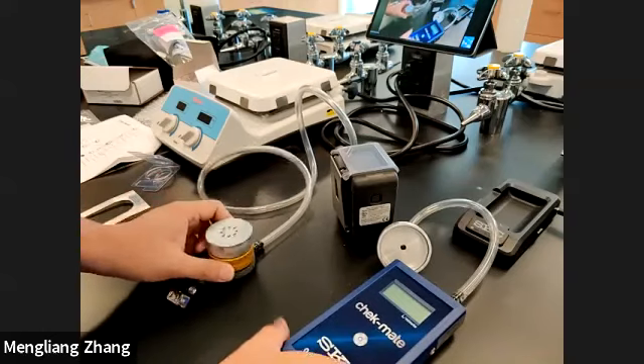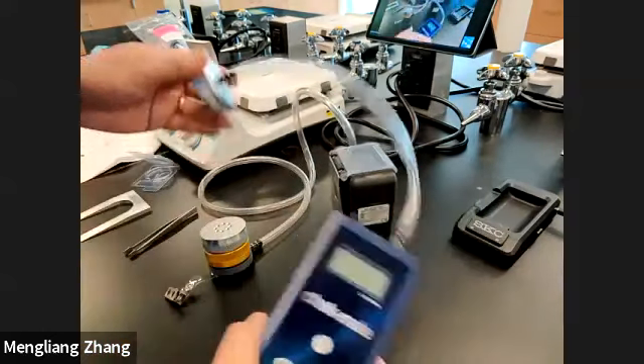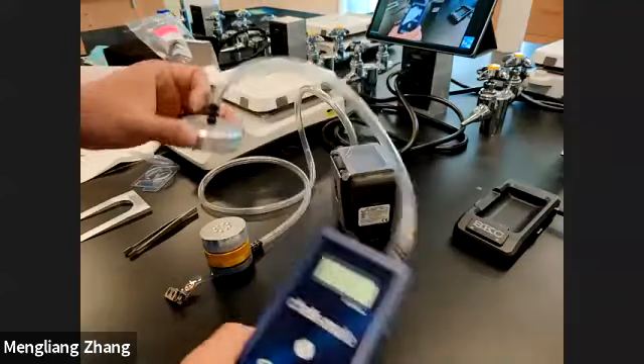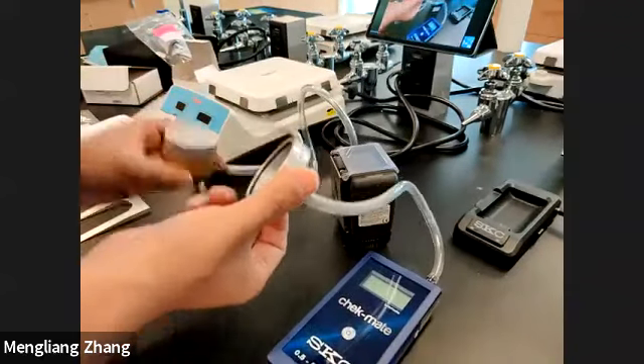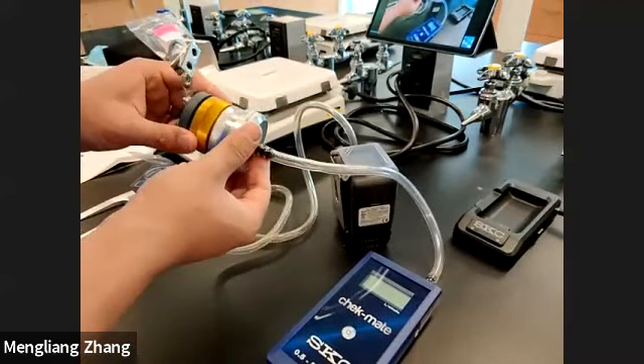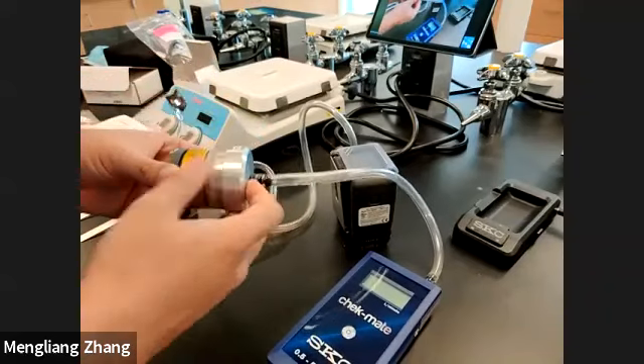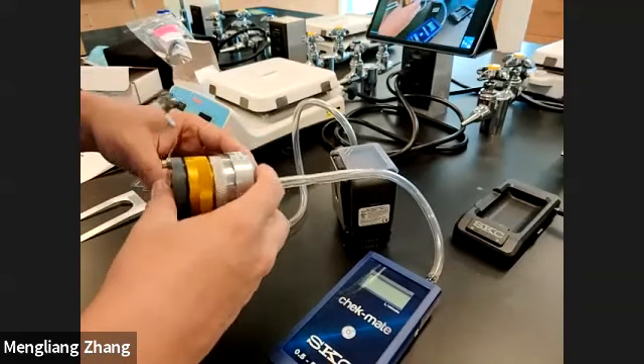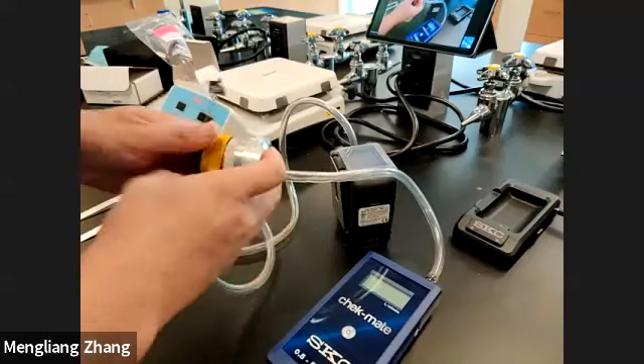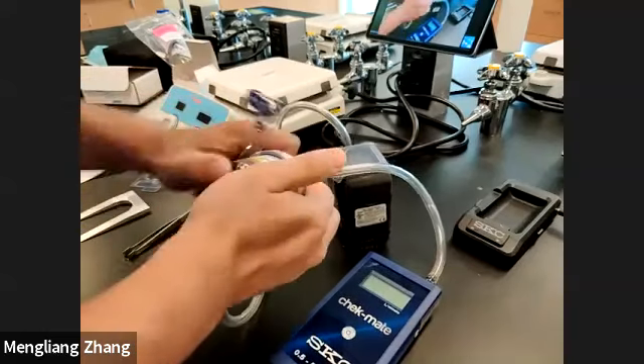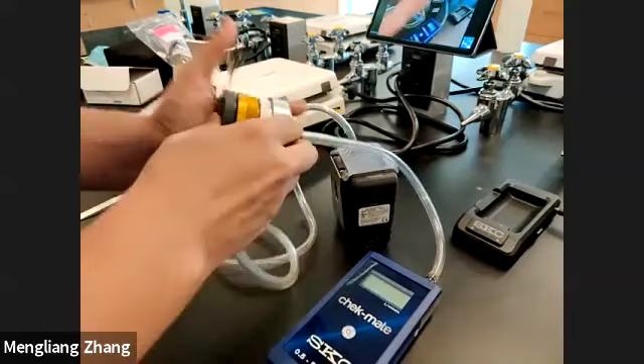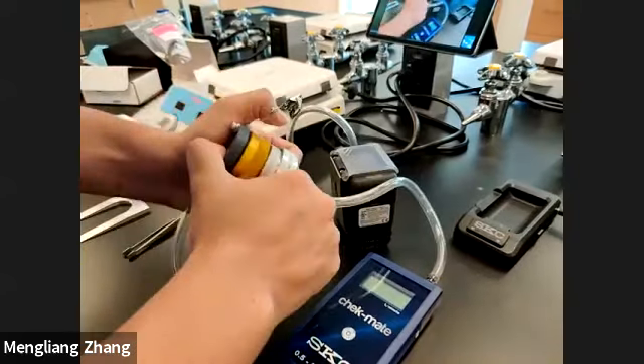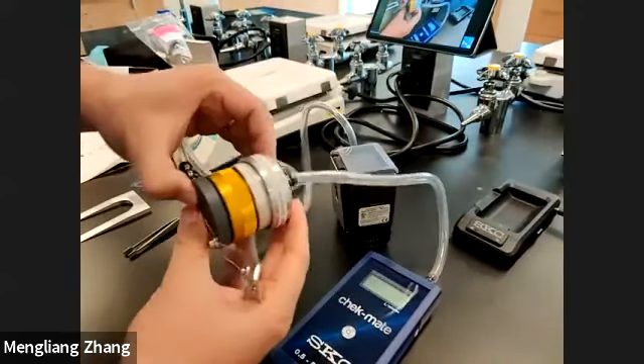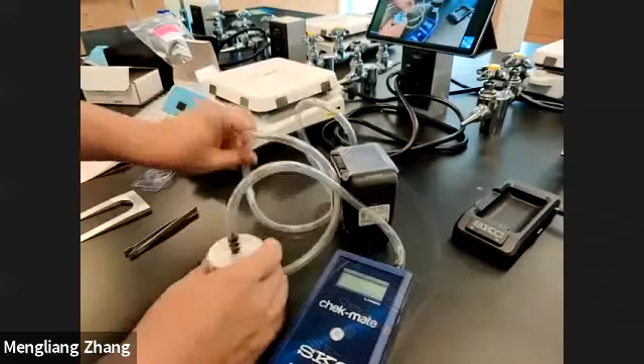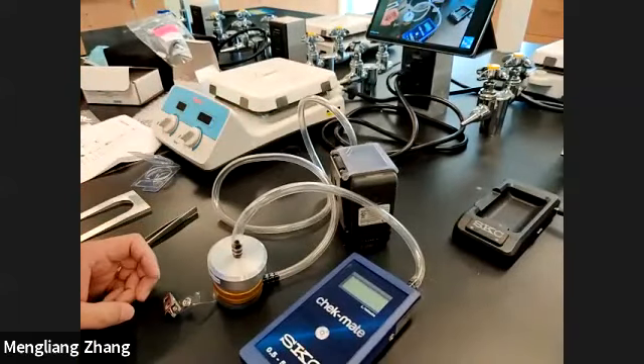The calibration itself is quite straightforward. You can see this calibrator has an adapter. All you need is to connect this adapter to the top of this impactor. So just click and connect it, and then press it. Make sure it's all the way to the adapter. Okay, so press it. You can see now it's all the way to the adapter. Then we can turn on this calibrator.